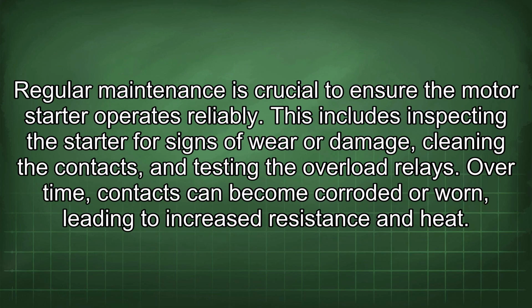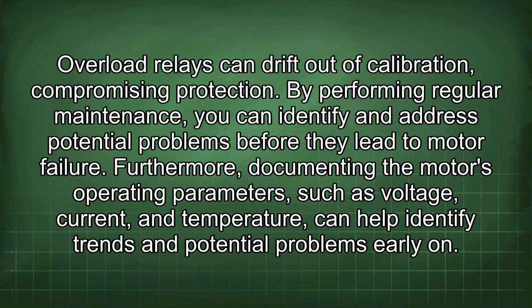Regular maintenance is crucial to ensure the motor starter operates reliably. This includes inspecting the starter for signs of wear or damage, cleaning the contacts, and testing the overload relays. Over time, contacts can become corroded or worn, leading to increased resistance and heat. Overload relays can drift out of calibration, compromising protection. By performing regular maintenance, you can identify and address potential problems before they lead to motor failure.